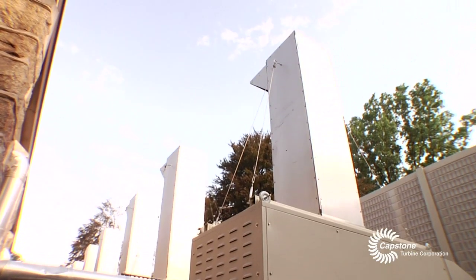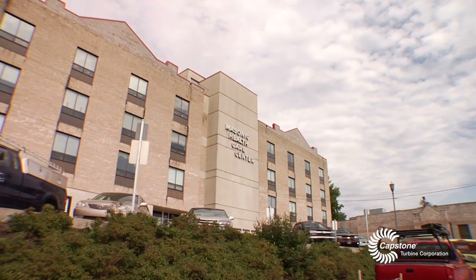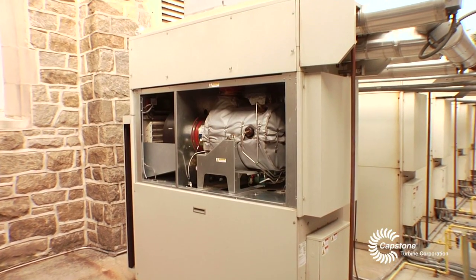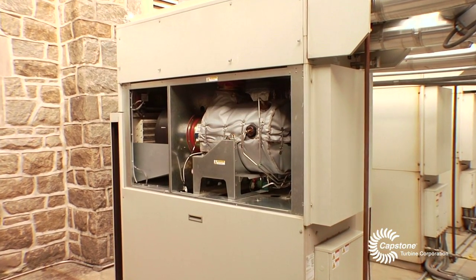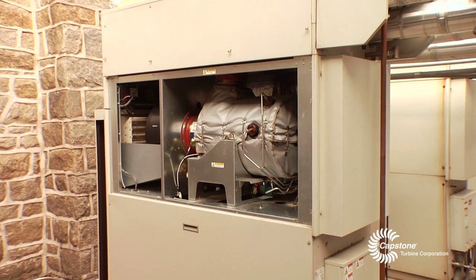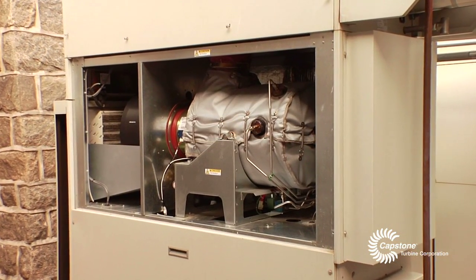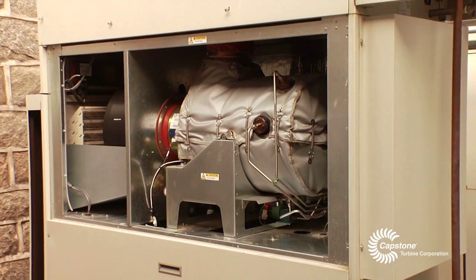It's not just the fact that we're generating electricity, but we're also using the exhaust to preheat and deal with our domestic hot water right here in this building, and also up at our health care campus — and that's what really makes the payback work. You look at the BTUs in, BTUs out, and converting your kW to BTU, when you're talking 80 to 85 percent efficiency on that throughput, that's a pretty impressive number.